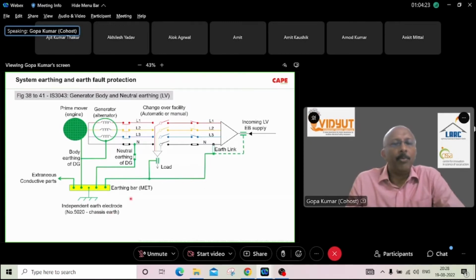This is how earthing has to be made in whatever the installation is, whether it is a house or residential, or hospital, or industrial, or commercial, or hotels, or whatever. The only meaning of earthing explained in the standards with pictures is to create an equipotential bonding system. That means all the metal parts in your building, except the current carrying conductors such as the phase and neutral, must be connected to a common bus bar. As a result, there is no shock voltage. Simultaneously accessible metallic parts don't carry any voltage.